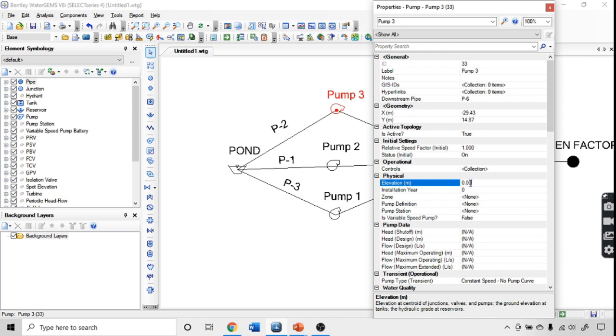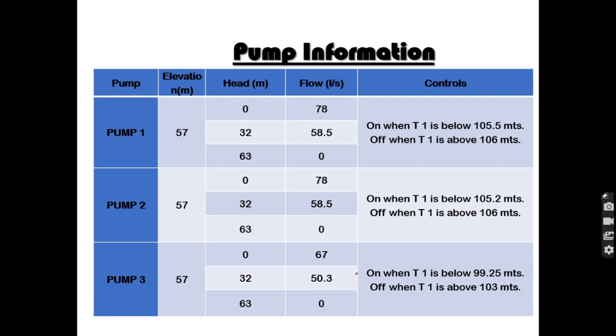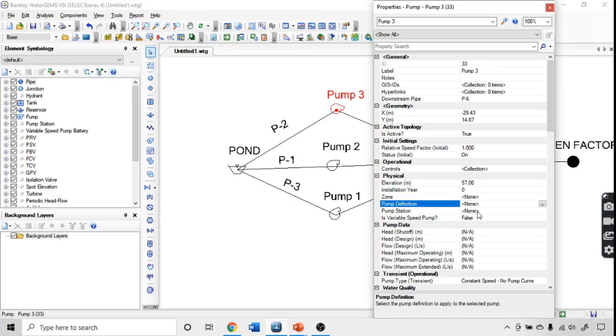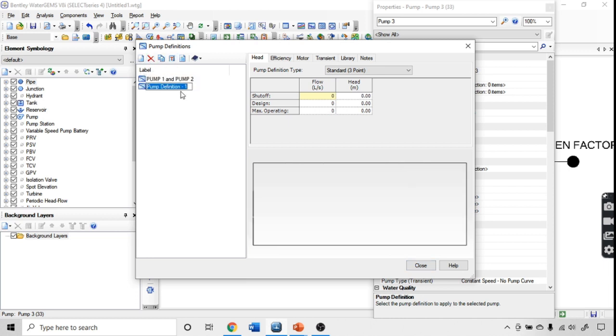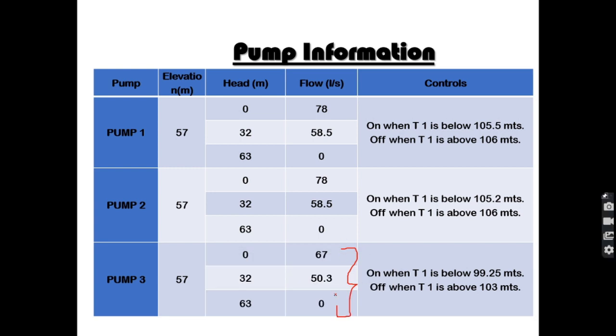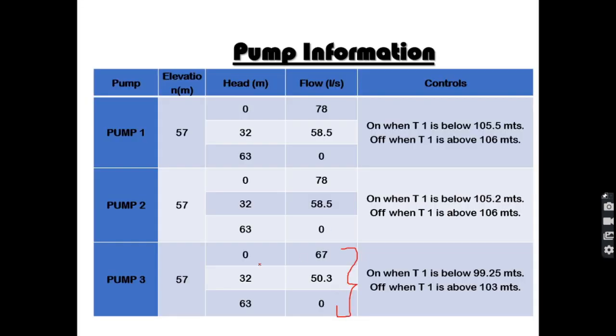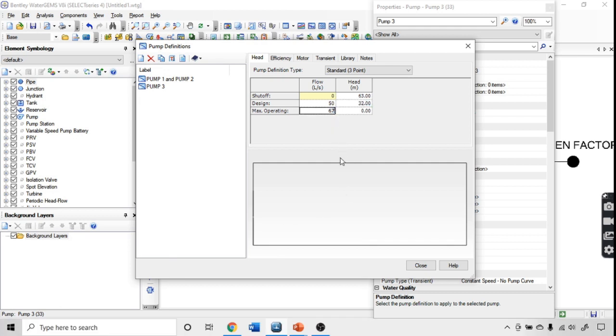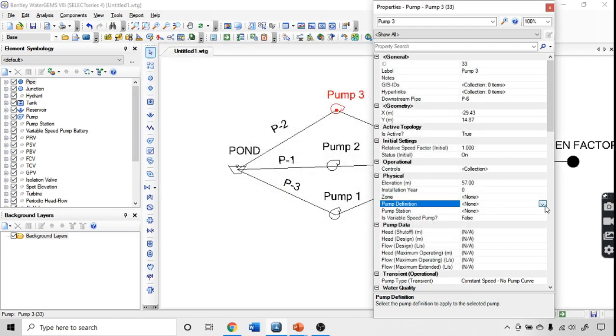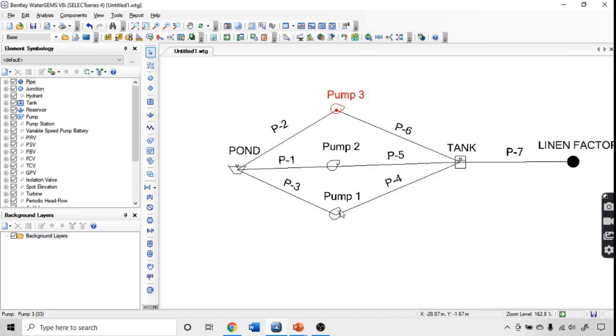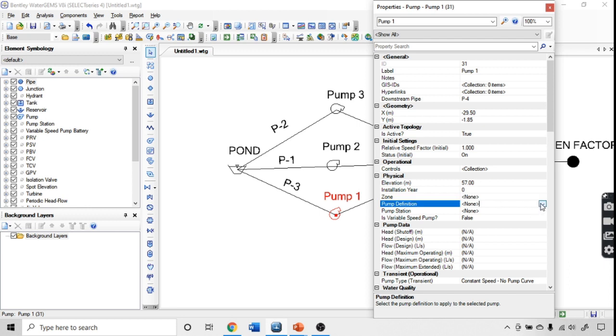For Pump 3, the elevation is also 57 meters, but its head-flow values differ. A new pump definition 'P3' is created with the following values: at zero flow head is 63 meters, at 50.3 flow head is 32 meters, and at 67 flow head is 0 meters. Pump 3 is then assigned this new definition. Note: don't forget to assign the pump definition to Pump 1 after defining it.